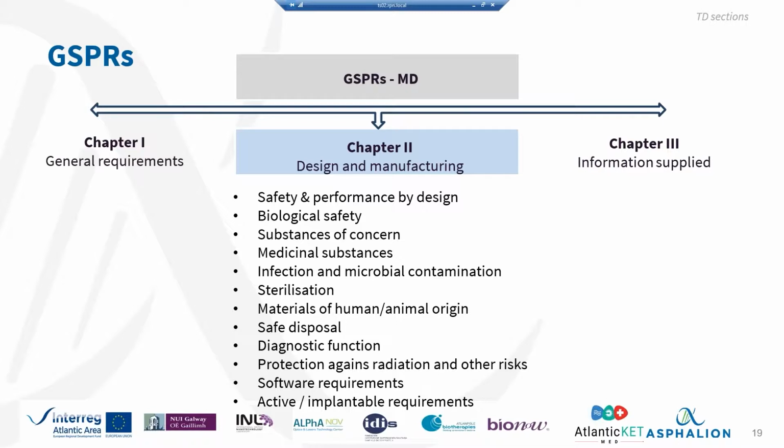Also, safe disposal. What does that mean? You've got to demonstrate that it's safe to dispose of your device. That means either retiring it, or retrieving it from the patient, or throwing it away once you have used it, or throwing it away when, for instance, it malfunctions. If you buy a device that has to be sterile and you find out that the packaging is damaged, it's got to be safe to throw it away without a risk to the user, okay, and to the environment, obviously.